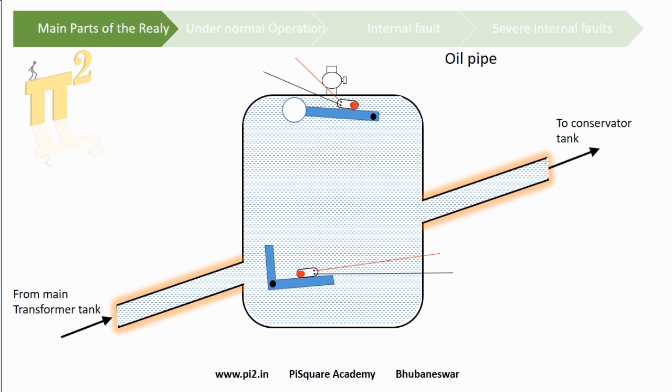We have an oil pipe connecting the main transformer and the conservator tank. Inside is the relay chamber and a test cock to collect gas samples. These collected gas samples can be tested, which helps in identifying the type of fault.